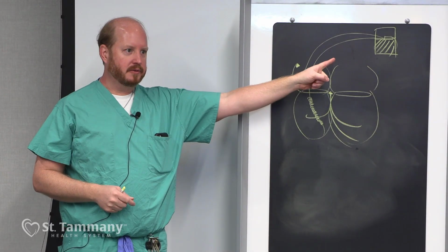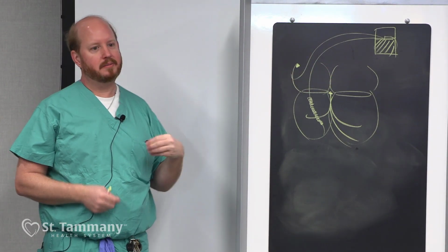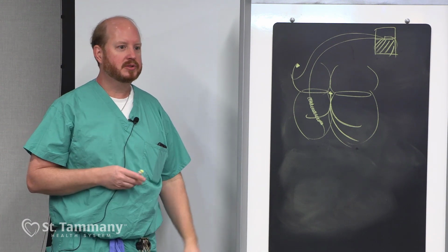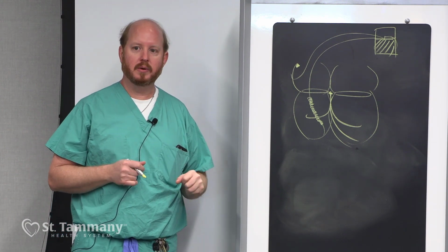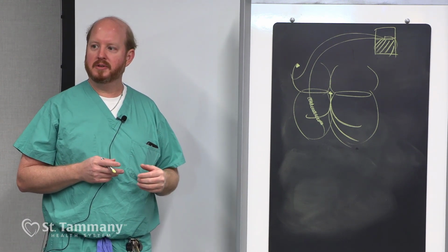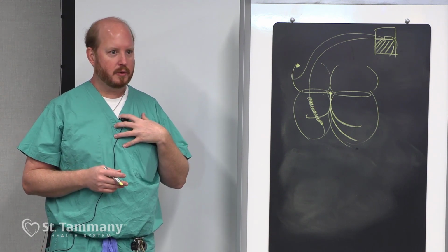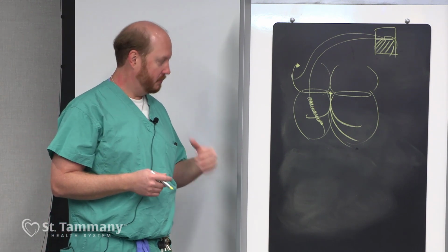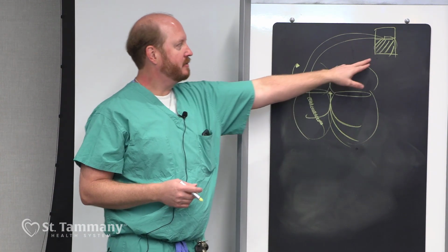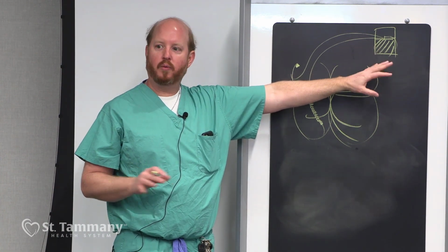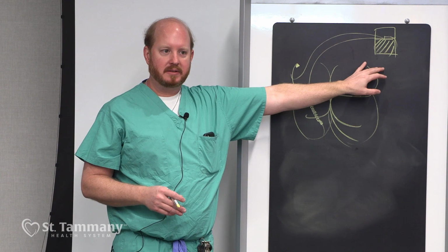That capacitor is the critical component of this defibrillator, despite having a little bit more going on in the chip, in the computer, to differentiate some stuff and make some decisions. It's all algorithmic. It's all stuff we control and can program. But that's just to know basic stuff of why these devices are different. So it has a capacitor.